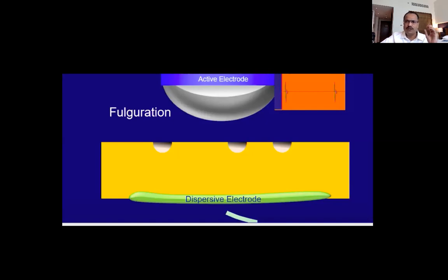So you saw three currents: cut current, coag current, and blended current. And you saw three tissue effects: vaporization, desiccation, and fulguration. The current is engineering language. The tissue effects are our medical language. But here we are going to use the words vaporization for cutting, desiccation for vessel sealing, and fulguration for spraying over a wide area.